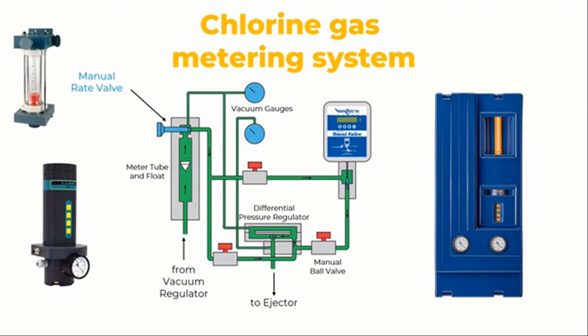Differential pressure regulators are intended to maintain vacuum. A chlorine gas system's objective is to inject chlorine into the water at a rate that will keep the appropriate residual amount of chlorine in the process water constant. To maintain the desired residual in the treated process water, the chlorine feed rate must be adjusted when the water flow rate and water quality change. In systems where both the process water flow and water quality are consistent, manual feed rate control is an option. It is advisable to utilize an automatic control system if the water flow rate or water quality are variable.